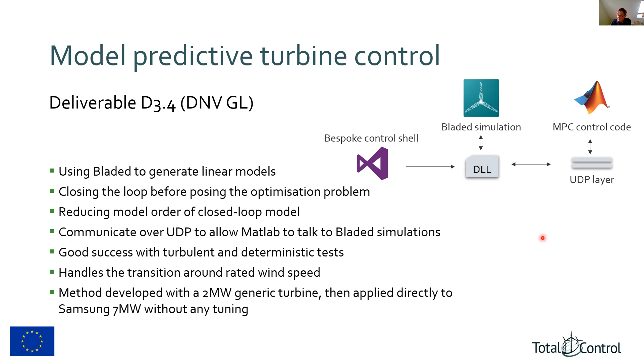This was quite successful by closing the loop before posing the optimization problem. You really simplify some aspects, and this worked very well, especially for handling the transition around rated, which is a very non-linear moment on the control curve. This was developed for a 2 megawatt generic turbine and then applied directly to the Samsung 7 megawatt model without any tuning, so that worked very well.